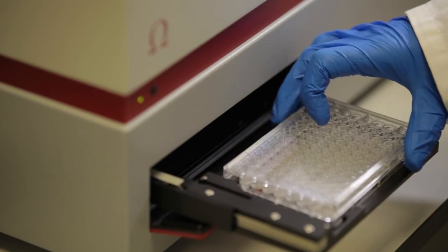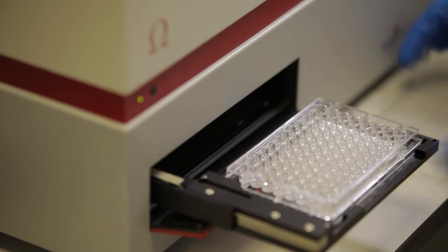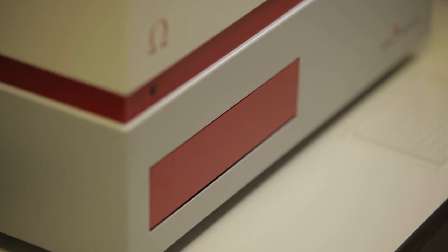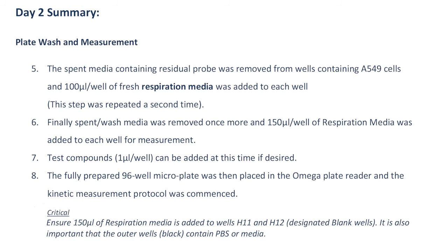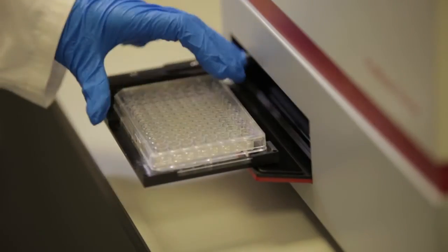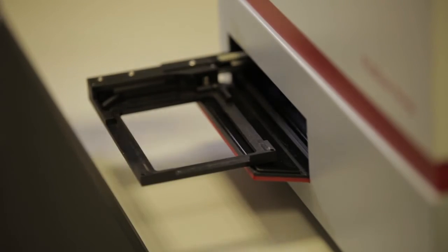In this particular instance, we're using the Fluostar Omega offered by BMG LabTech. The instrument should be turned on in advance to allow for temperature equilibration. This plate reader has been programmed to the correct measurement parameters. The plate is measured kinetically, typically for 30 to 90 minutes, but can be measured for longer. Drug treatments can be applied during the measurement by pausing the instrument, withdrawing the plate, making compound additions, and then resuming the measurements.